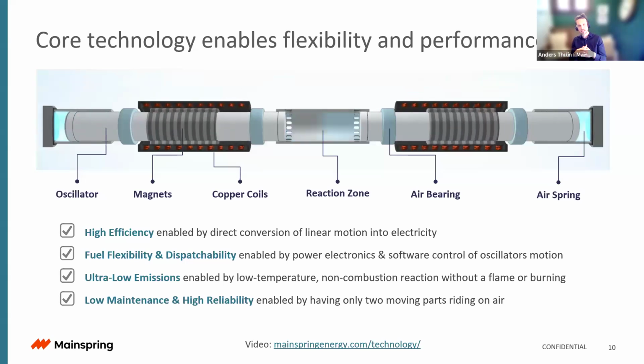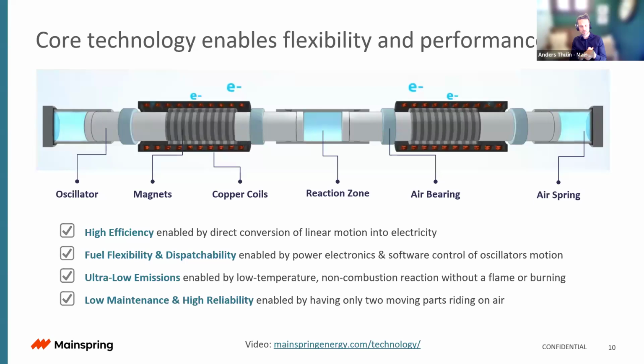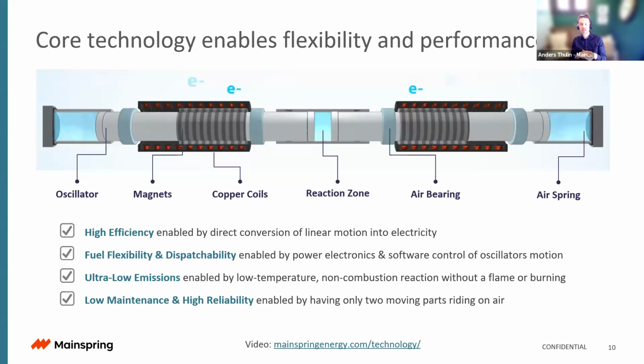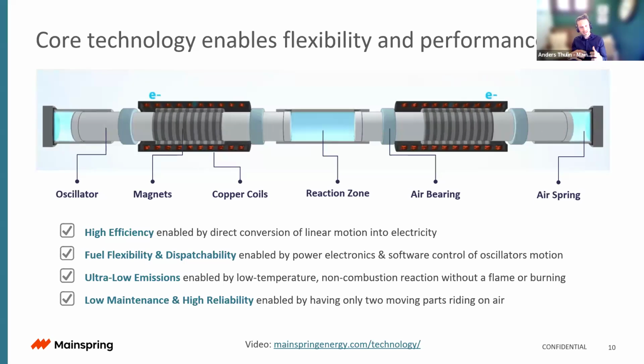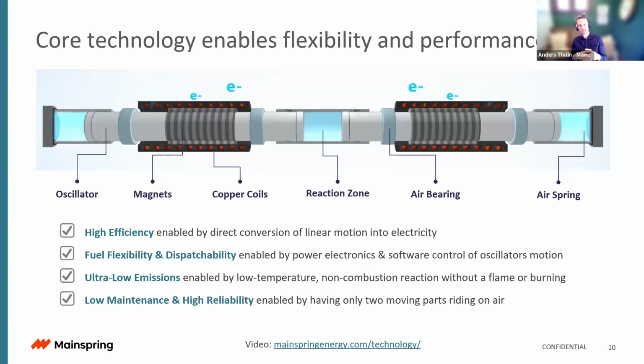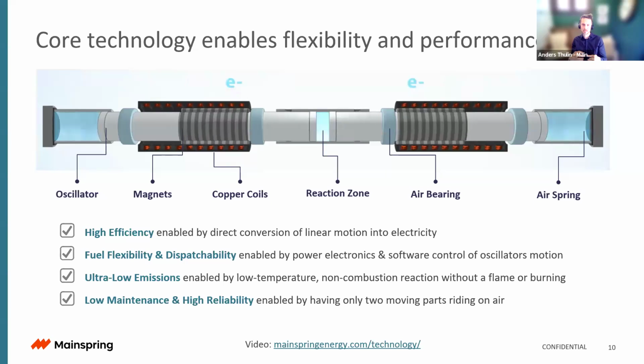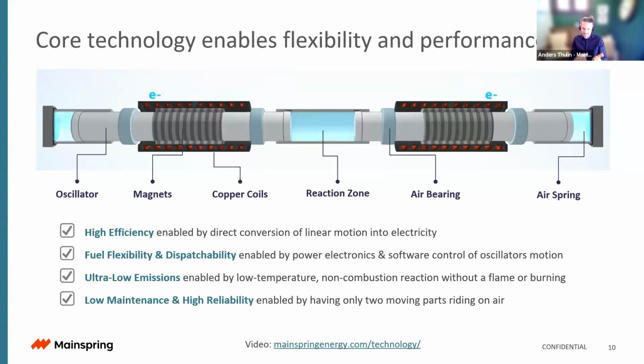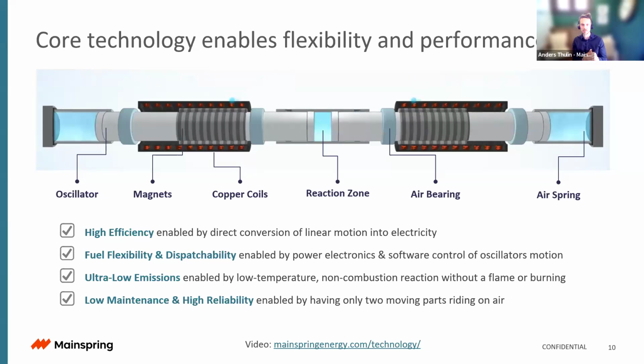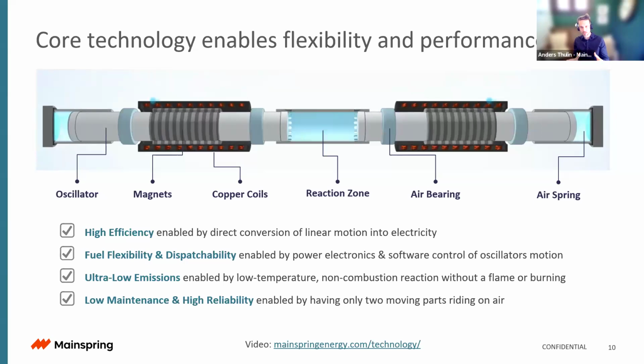Those hot pockets can exceed 2,500 degrees Celsius, creating significant NOx formations. Here, everything stays below 1,500 degrees C in a homogeneous temperature reaction. So you don't have hot pockets, you can stay below 1,500 C, and therefore avoid those NOx emissions from forming. The other thing to consider is the efficiency of the system.